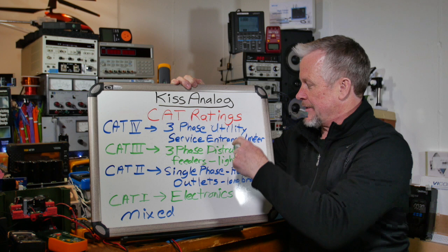Up here, you can see Category 4 and Category 3 are both 2 ohms, but this one's 3,000 amps, this one's 4,000 amps. So that's the difference, about 1,000 amps. Significant probably, right? Now, Category 2, you can have 6,000 volts, but it's 12 ohms, so it's like 6 times less current? So it's a big drop from 3 to 2. That's kind of the point I've been trying to make. So anyway, those are the levels of surges, and this is the ohms.